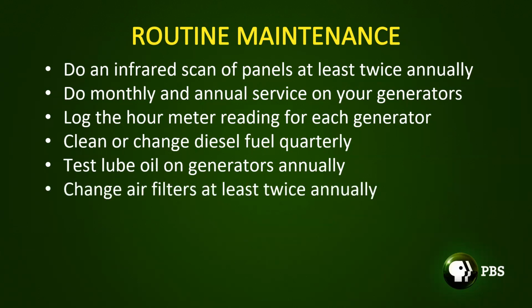Change air filters at least twice annually. Now, I'm talking about the air filter for the combustion air of the emergency generators. Those things clog up very quickly, particularly when you're out in even an urban environment. We have a problem here with the sediment that's created by car tires running on the Beltway, which is about 1/8 of a mile from us, and it clogs up filters really quick. Obviously, if you don't have combustion air, they're not going to start.